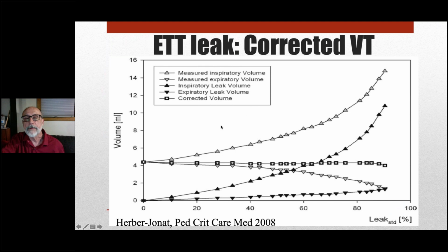One of the reasons people talked about was concern about leak around the endotracheal tube. And it is, of course, an issue when you have a large leak around the endotracheal tube, and this is a study published a number of years ago that looked at what happens when you have progressively larger leak. There are other similar studies, and you can see that the inspiratory tidal volume goes way up as leak goes above roughly 40% or so. Expiratory measured tidal volume deviates less from the actual tidal volume.